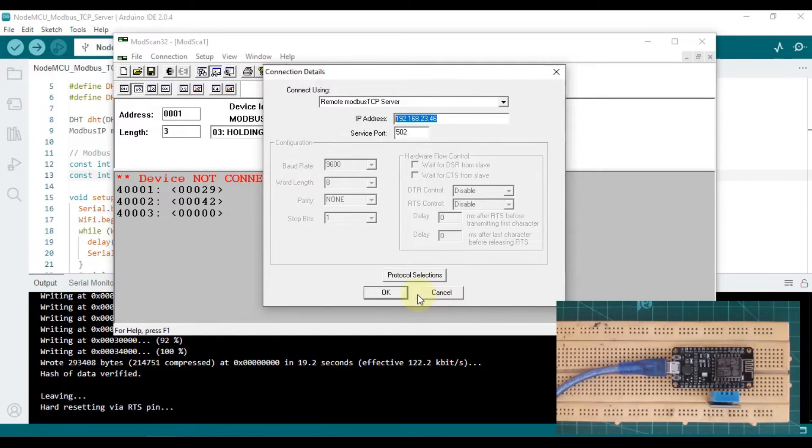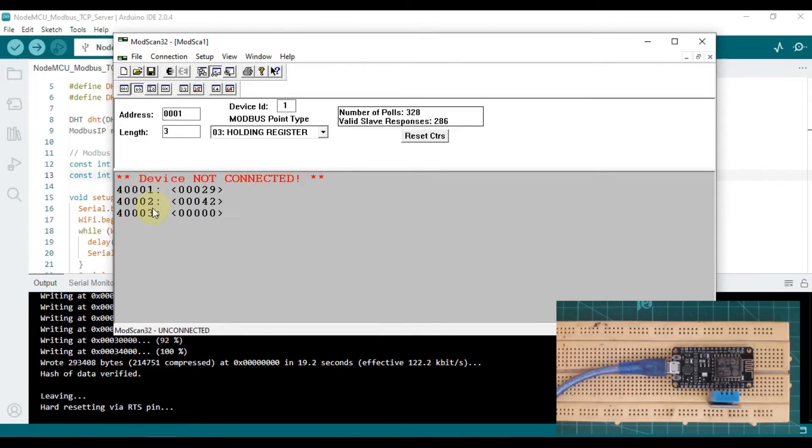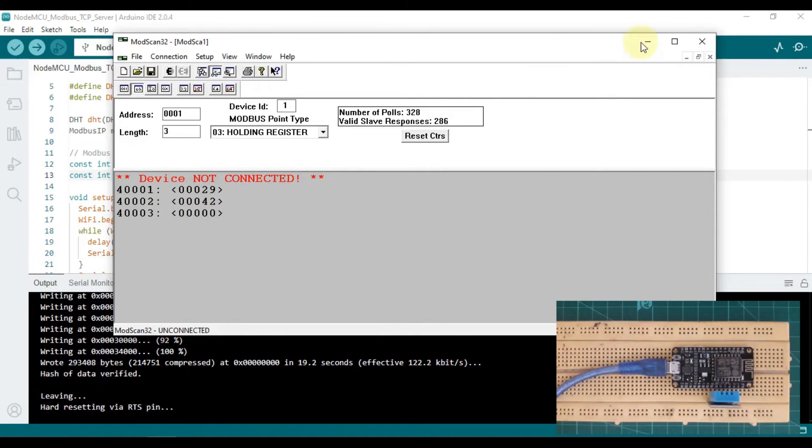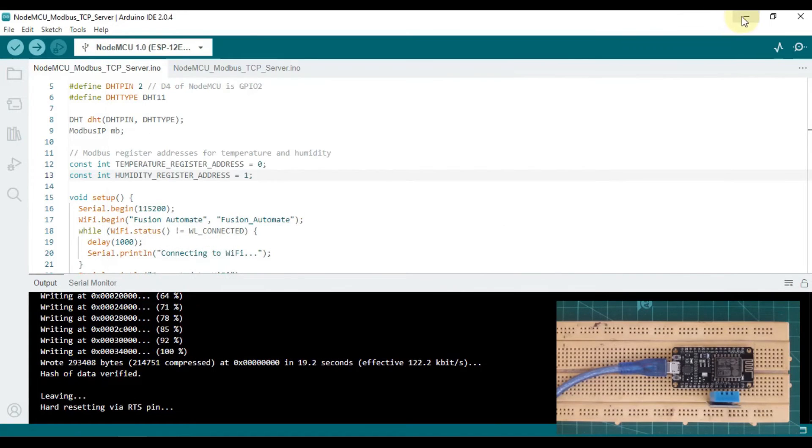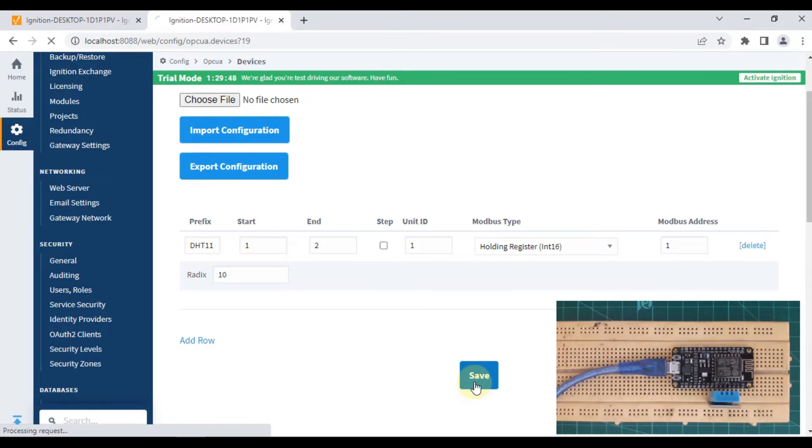As you can see here, temperature is at 40001 and humidity is at 40002. You can also see that in our ModScan software, temperature is available at 40001 and humidity is available at 40002. So we have to use one here, and it will read from 40001 and 40002. We'll save this.